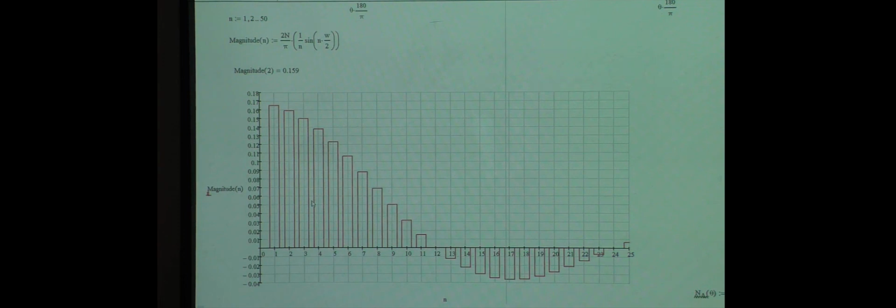So if you're designing a concentrated winding machine, you have to be very careful with regard to minimizing the losses in the magnets. For example, you need to almost certainly segment the magnets. So rather than one big magnet, you would have multiple magnets, and that would then reduce the losses significantly. Okay, I'll stop there.